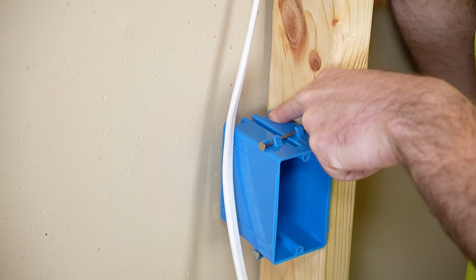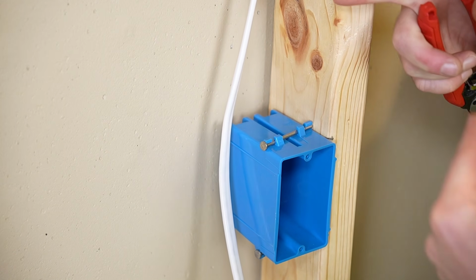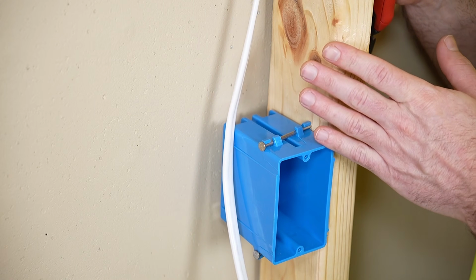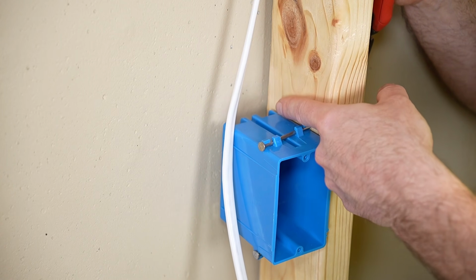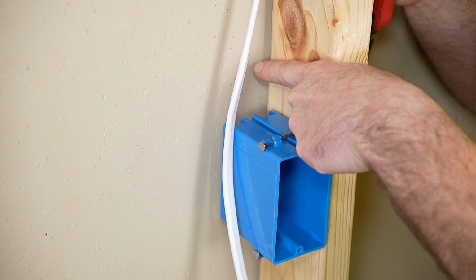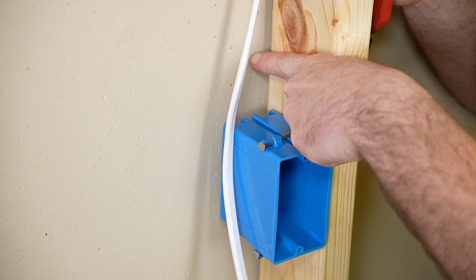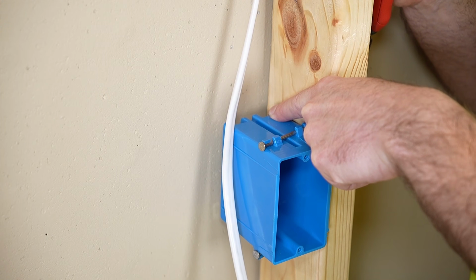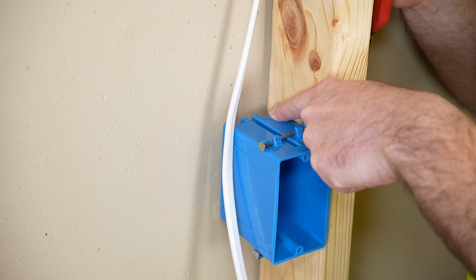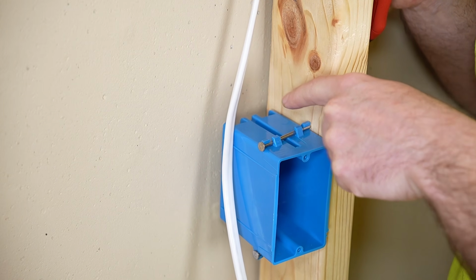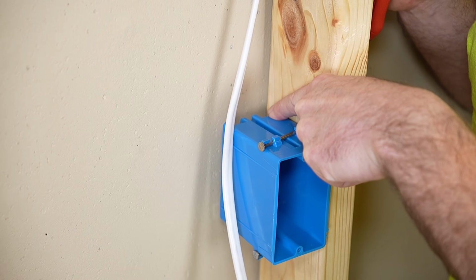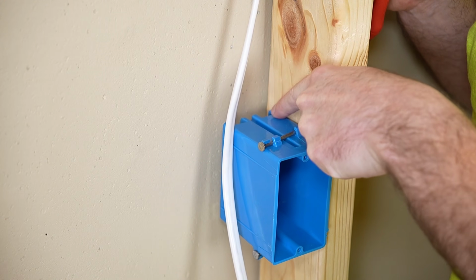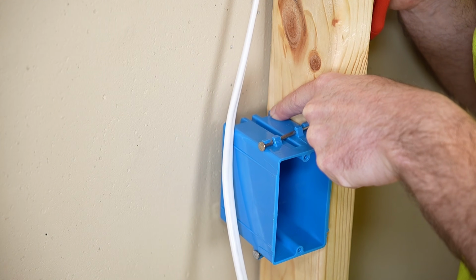You can use this closer knockout if the wall is deep enough. For example, with a 2x6 wall, there's enough distance from the face of the sheetrock on the backside to this knockout that it would be acceptable—I believe at least 1.25 inches from the back of the box to the face of the stud before you're allowed to use it.